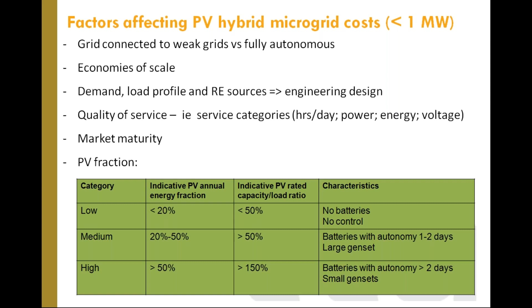Another factor that affects cost is what we call the renewable energy fraction in a hybrid PV plant. It could be that you just complement and offset part of the fuel consumption, with the genset almost always on, or the genset could be off and used only for backup. This impacts the investment cost because you need more batteries.